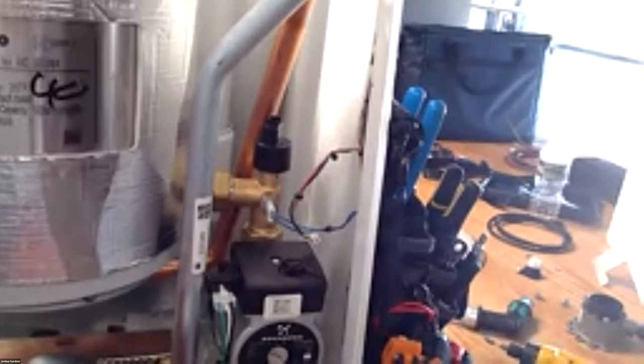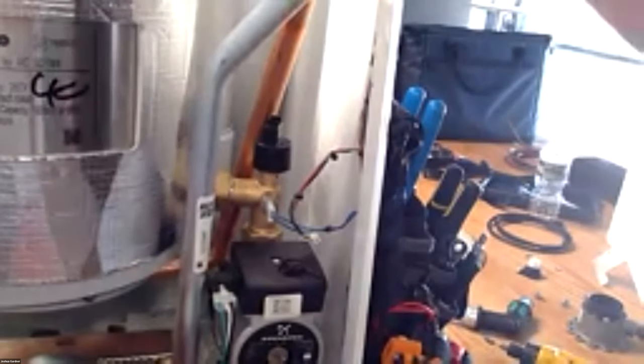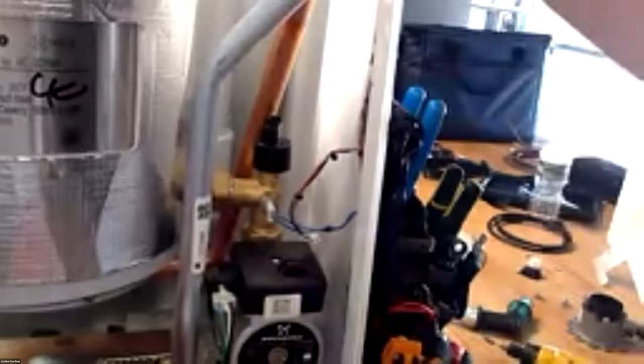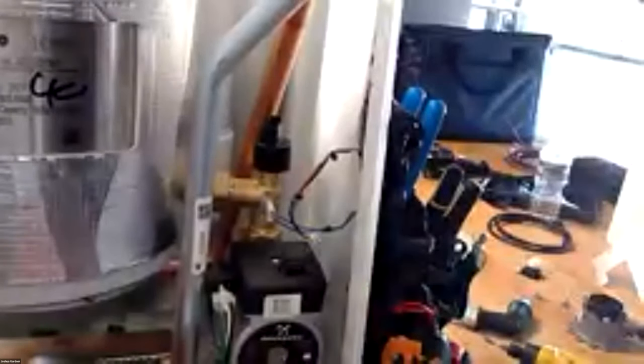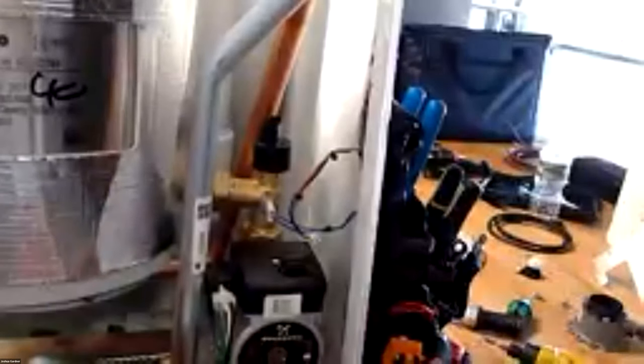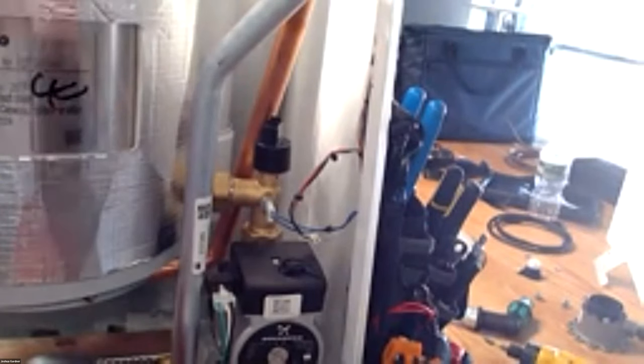There's an inlet screen on the gas valve. So if you have gas issues and you're scratching your head, and pressure looks good but you're getting drops, you can always pull this off and check the inlet screen. There's no inlet screen on the domestic, so you don't have to worry about anything clogging up there. Polarity. That's about it for the service.